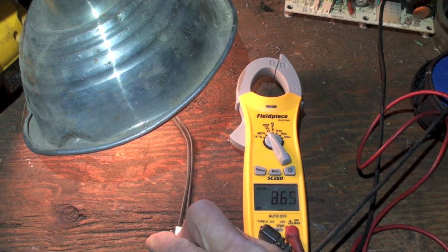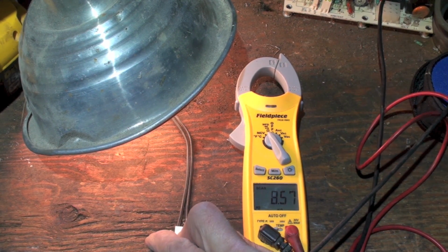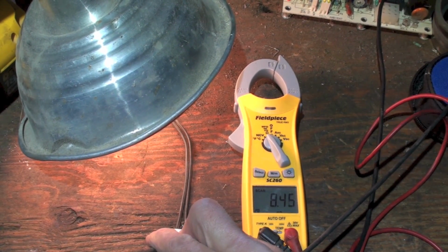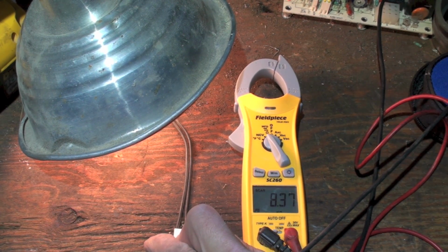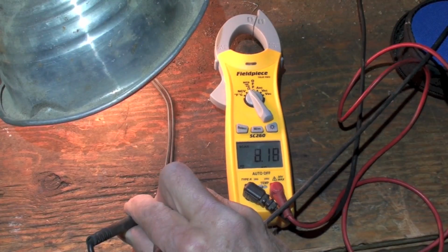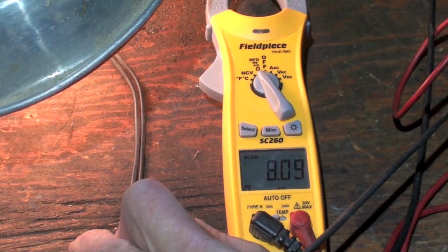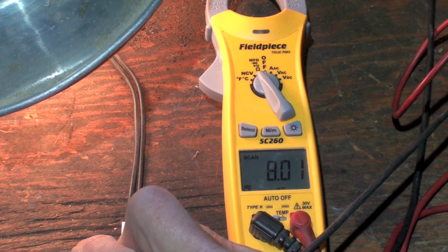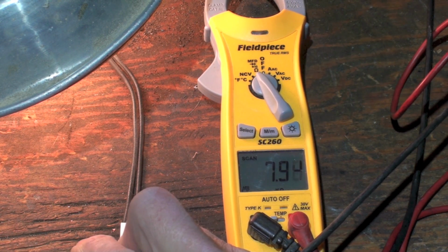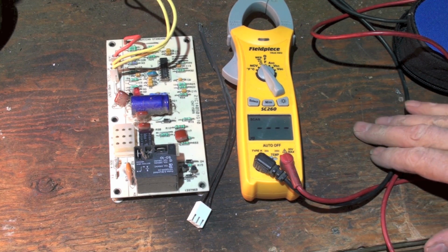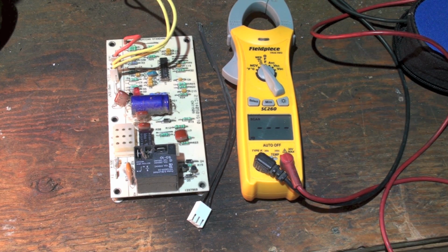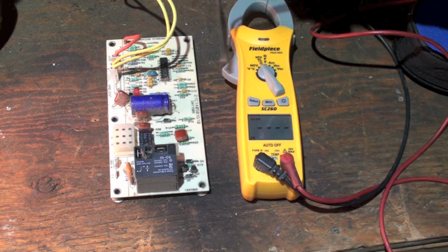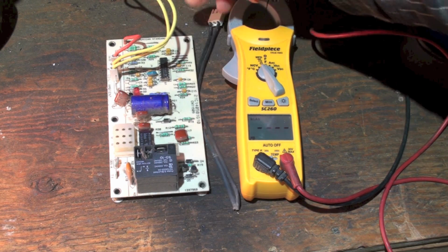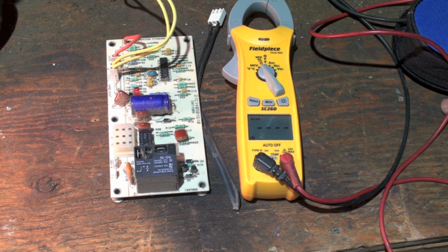Now, if you note, I put an incandescent lamp right here playing onto the probe, and you can see the resistance is dropping as we go here. You start out around 12, and as it warms up, it's going down. Okay, if you're going to test one of these things out, you say it's frosting up, or it's not going into defrost, or something like that. One of the first things you can do is test the probes. You're going to have to use manufacturer's instructions to tell you what the resistance should be.